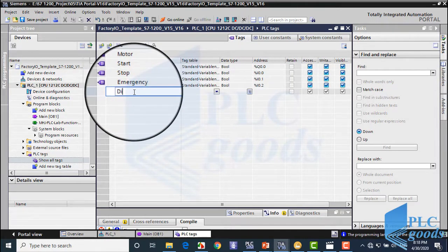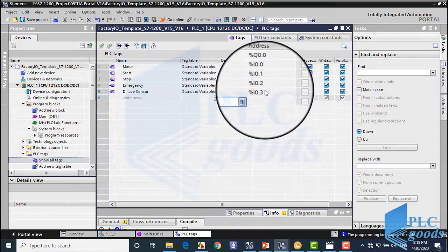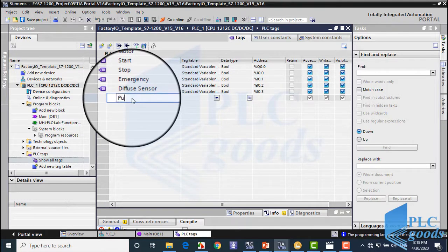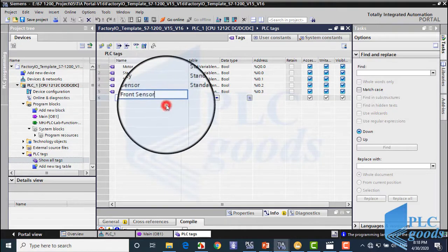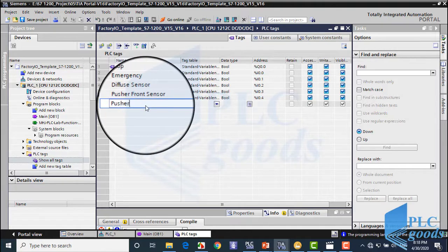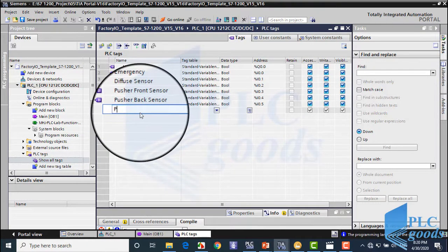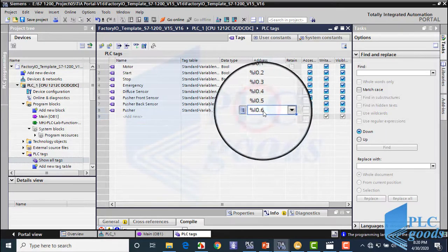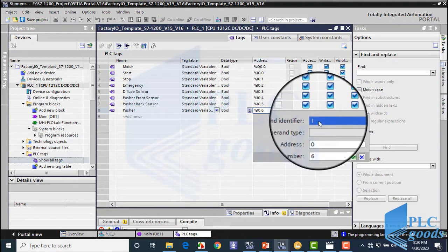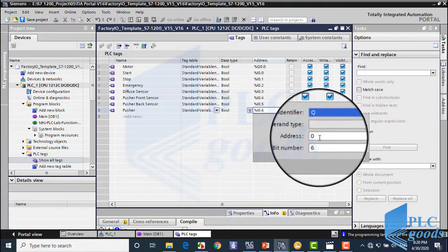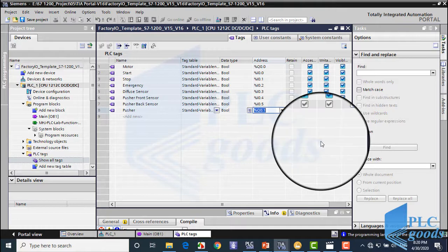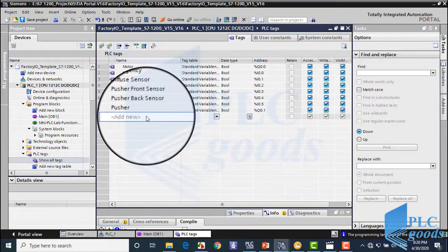The diffuse sensor is connected to I0.3 of PLC input. Next, PLC inputs connect to the pusher sensors — its front and back limit sensors. Pay attention: when defining tags, each tag in the address column automatically gets an address right after the previous one. Based on your PLC wiring, if a related device is connected to another input or output, you must modify its address in the column. The pusher must connect to a PLC output, not its input. Q0.0 has been used for the belt conveyor motor, so I'll connect the pusher to the next PLC output, Q0.1. I'll also connect other actuators to the next PLC outputs.